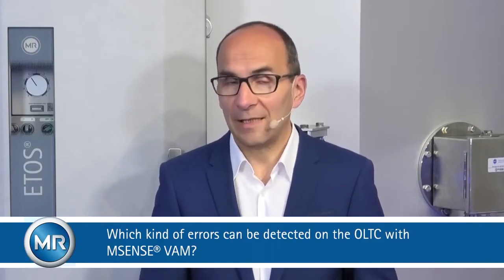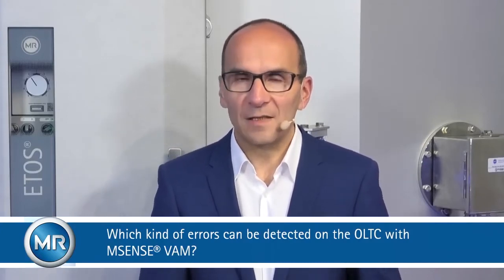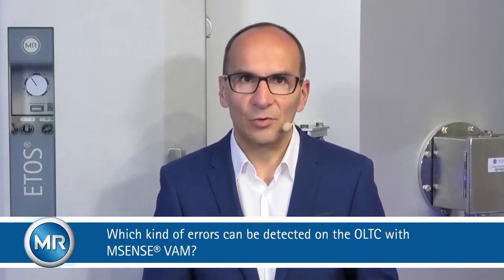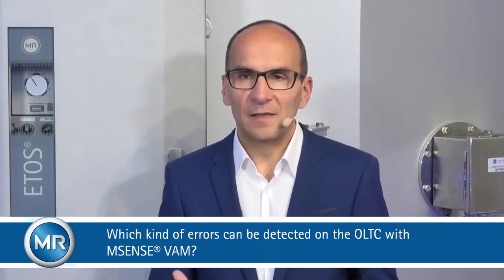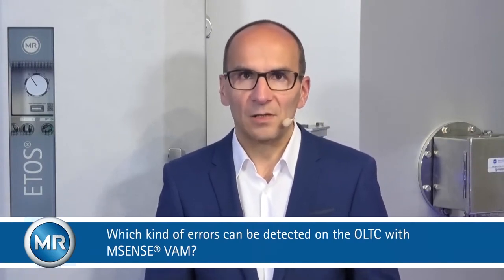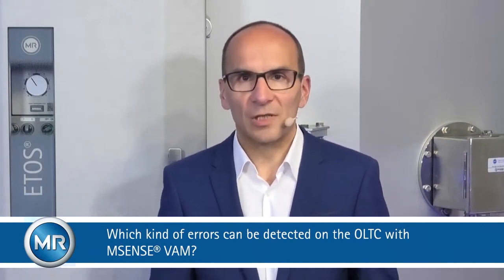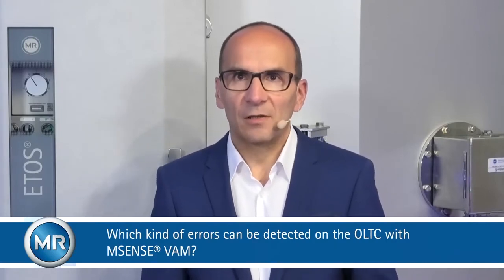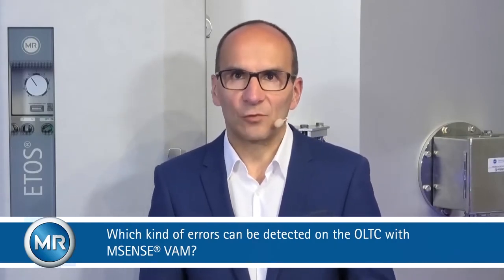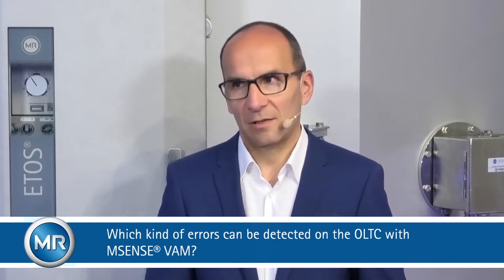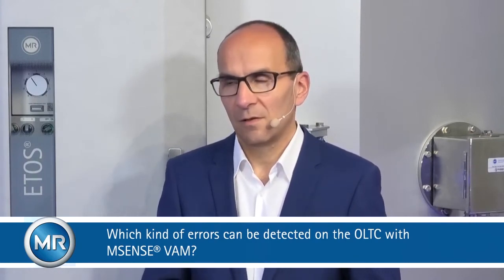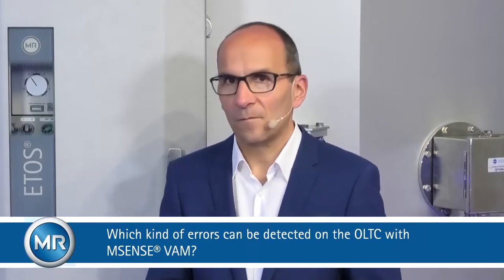And as I say that, during that further analysis, of course, MR supports you in analyzing the detailed sound and vibration patterns and allows, together with our experts, the analysis and determination of root cause issues with that OLTC.